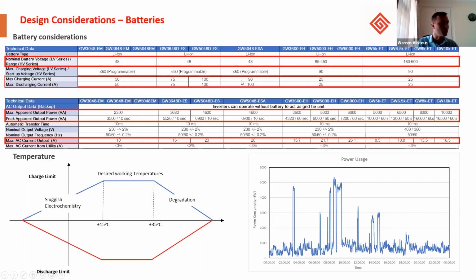Very similar for GoodWe's ESA. It's 90 amps charging max, but 100 amps discharging. And then very important, with the EH and the ET series, is a max charge and discharge of 25 amps. So to achieve your maximum outputs on the inverters, we need to achieve the right voltage in the batteries to get that. So you would have to stack enough batteries in series to achieve the full load output.